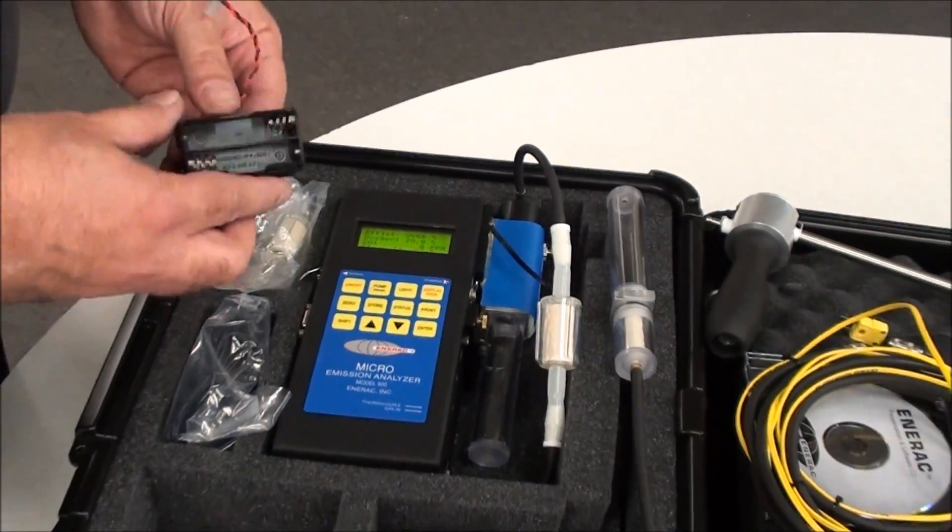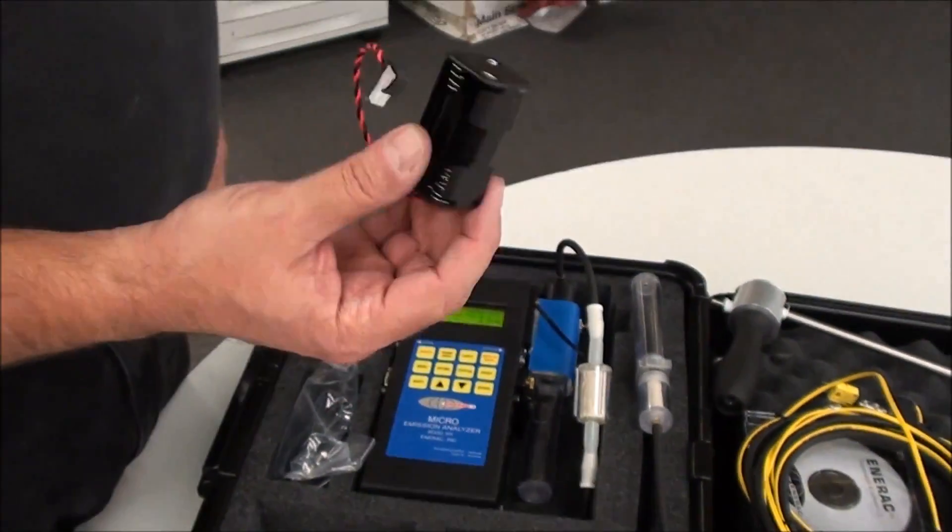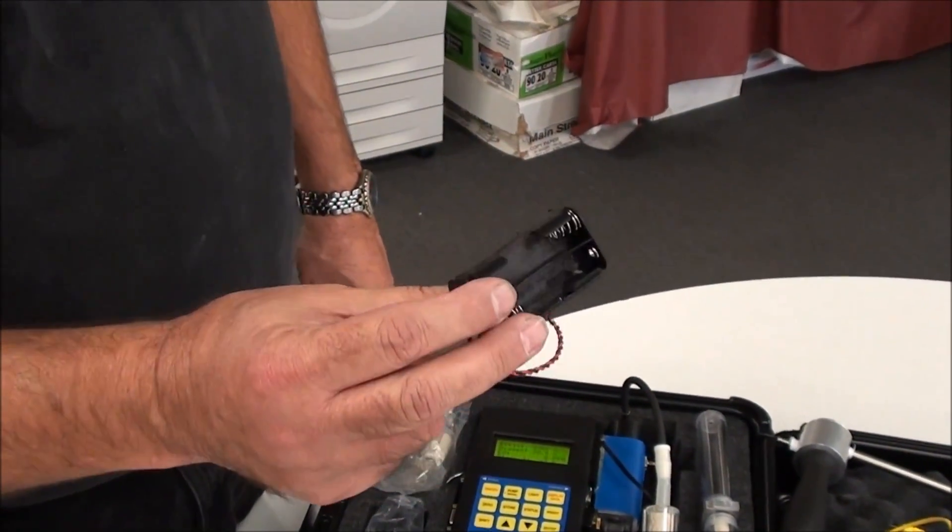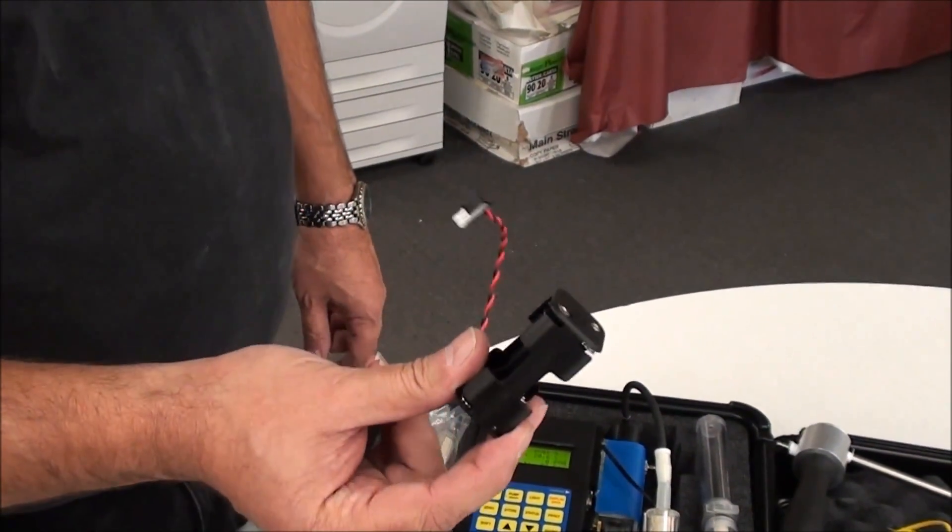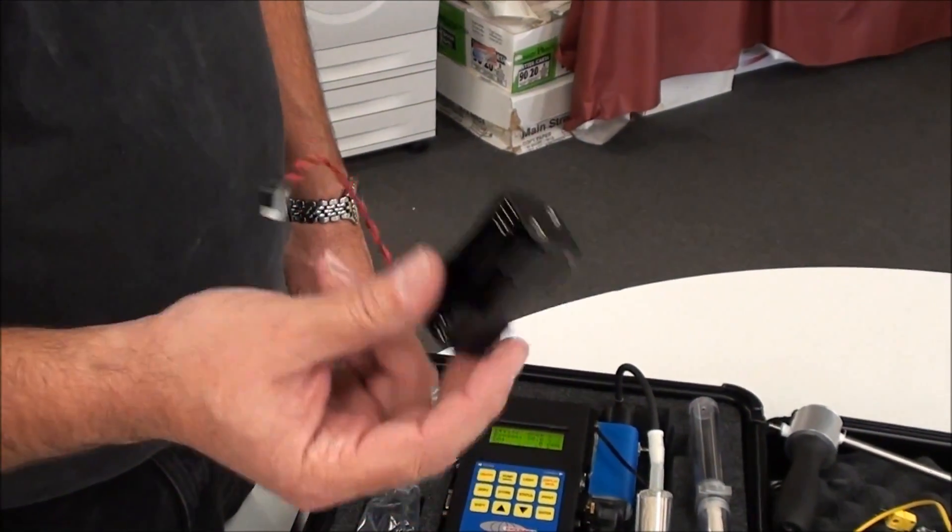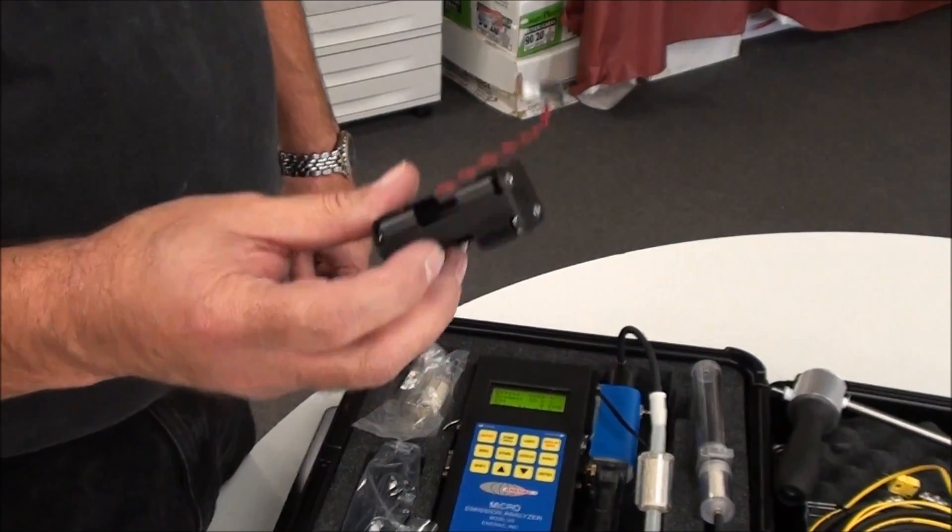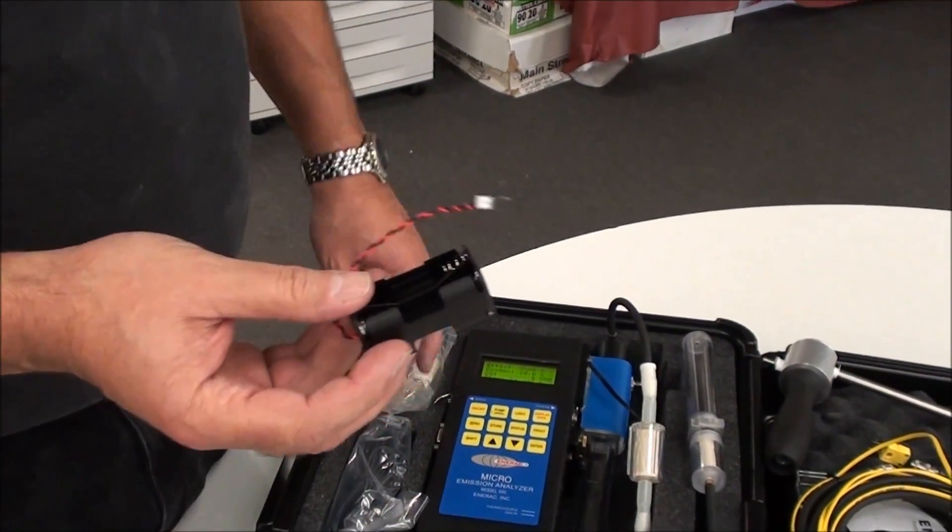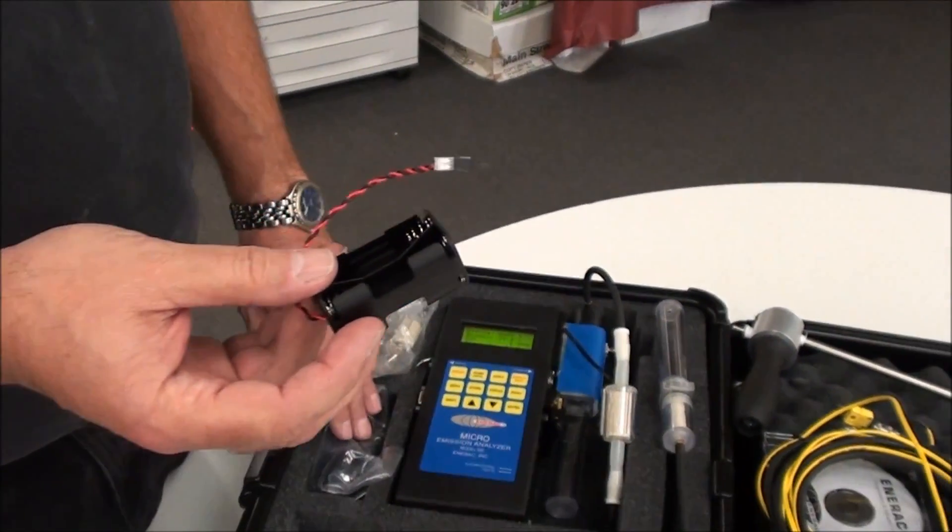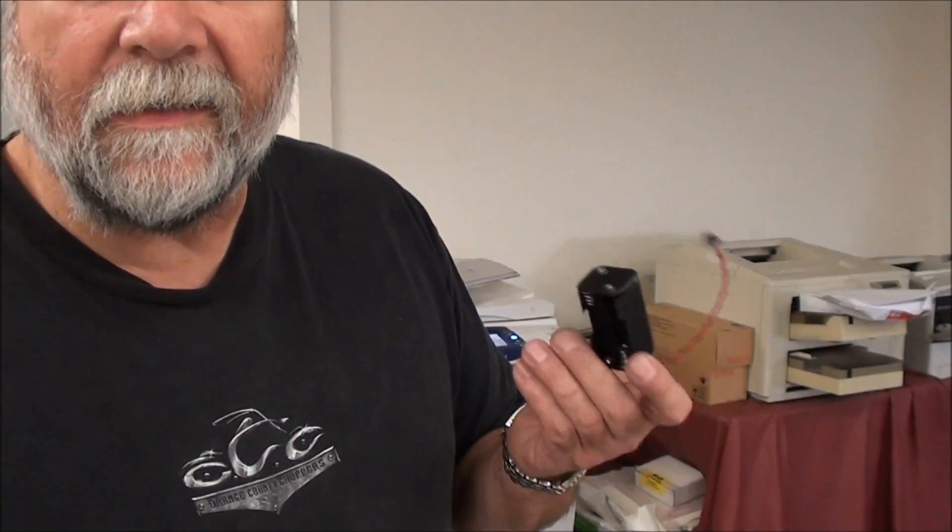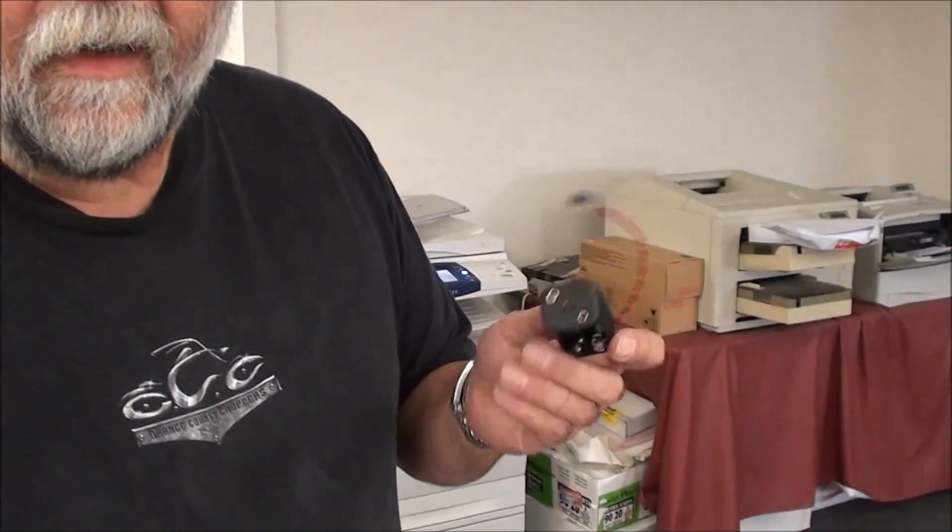You also get a 4-cell, 4AA cell battery holder. In the event that you're in the field and you don't have power available to operate the unit on the rechargeable batteries, you'll install four alkaline batteries into the holder, and you can continue your testing. Plug it in, let the unit sit for about five minutes so that the sensors re-stabilize, and then you can continue your testing.